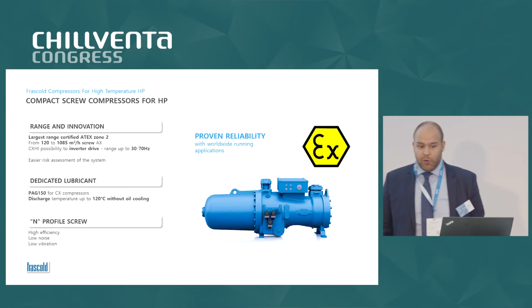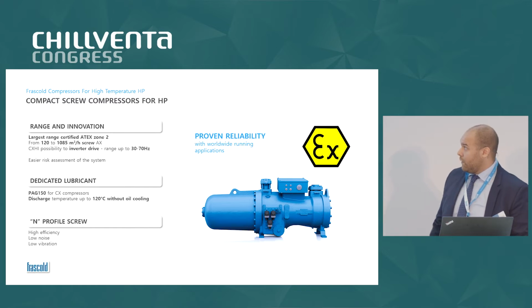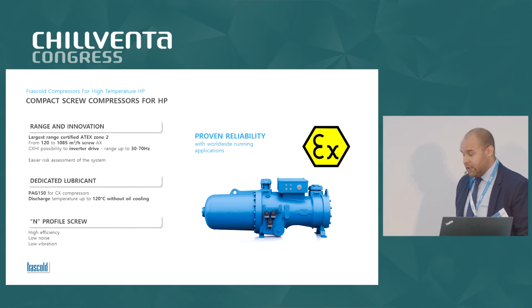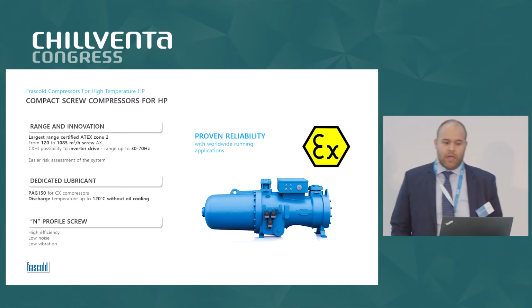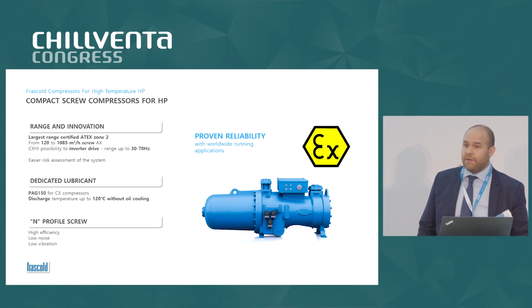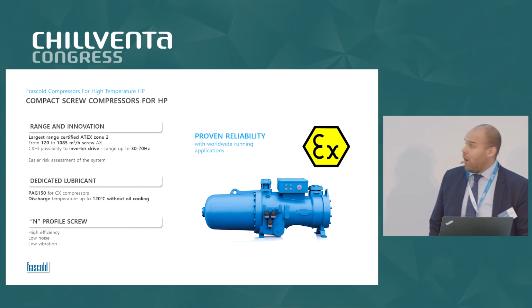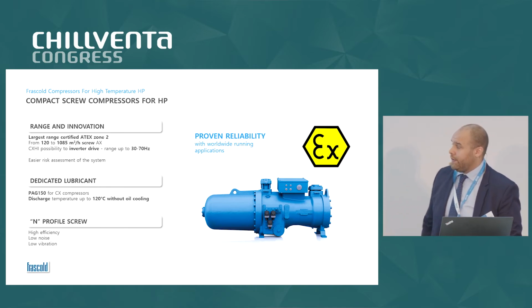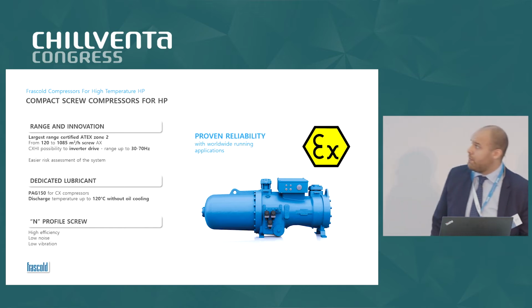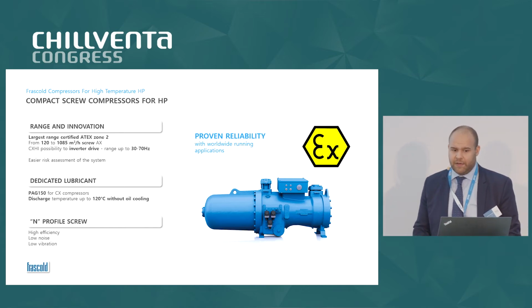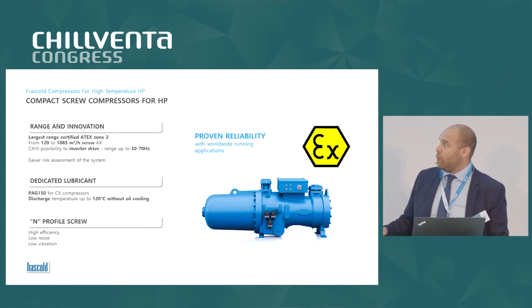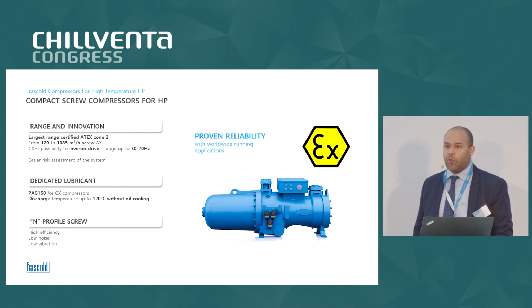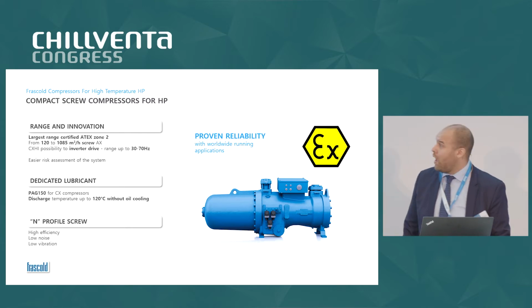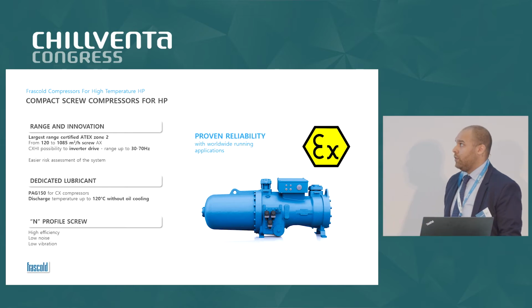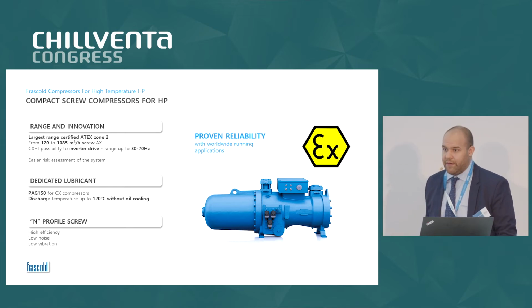This is the Frascold proposal for this kind of application: our compact screw compressors with ATEX certification Zone 2. We have the largest range certified ATEX Zone 2, from 120 up to 1085 cubic meters per hour, with the possibility to drive these compressors also with an inverter drive, with a range from 30 up to 70 Hertz.